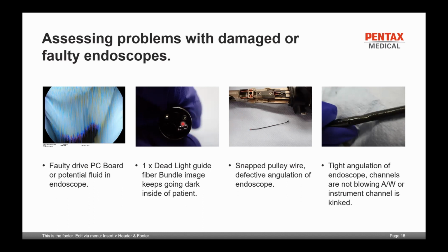The next image, sorry it's so dark, shows the 2 light guides. If you can see, only the one light guide is illuminated and the other light guide is not. So the way to check it is, if you have the endoscope connected to the processor and you switch it on and only one light is burning, you know you have a dead light guide fiber bundle. So if at any stage the endoscopist or the physician working with the equipment is complaining that the image is dark or it's casting a shadow, the first thing to look at is your light emission out of the tip of the endoscope.